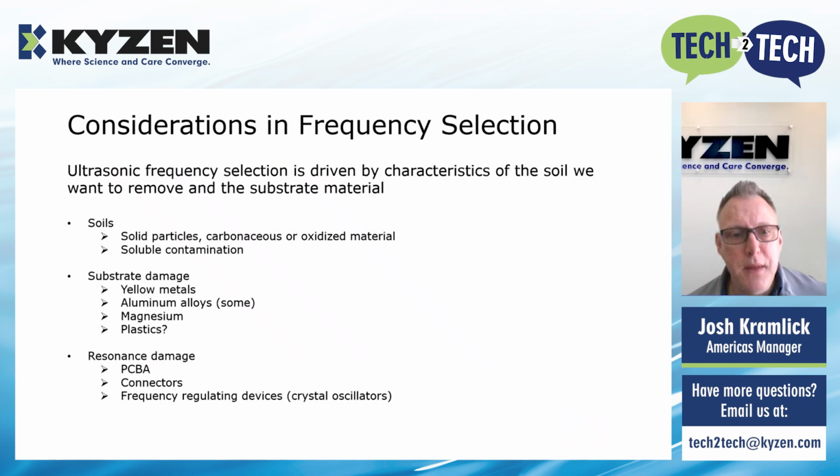And there's also applications where we need to consider resonance damage, such as printed circuit board assembly and connectors, and frequency regulating devices like crystal oscillators, where the functional frequency of those devices might actually be too close to the resonant frequency of the ultrasound that we're using.